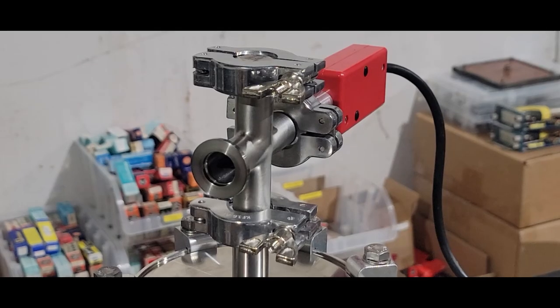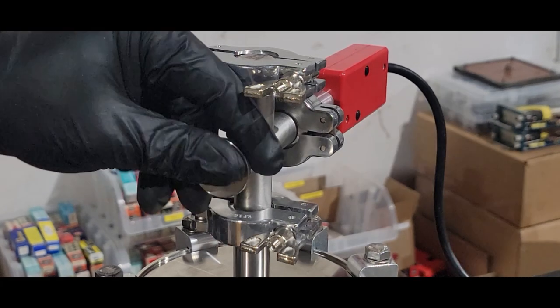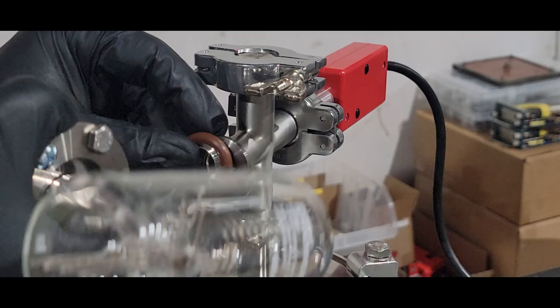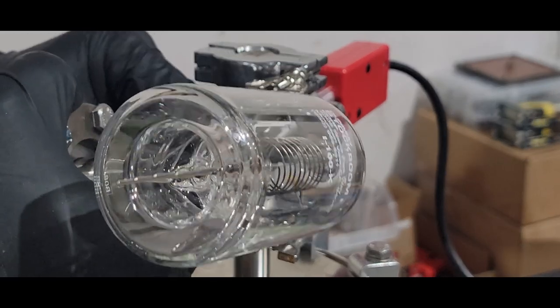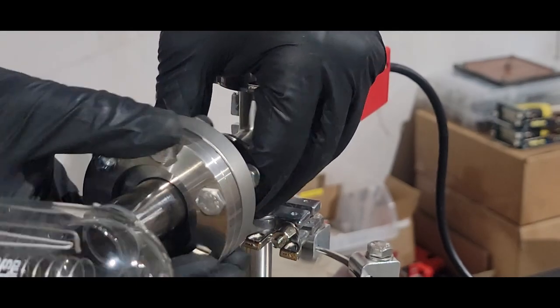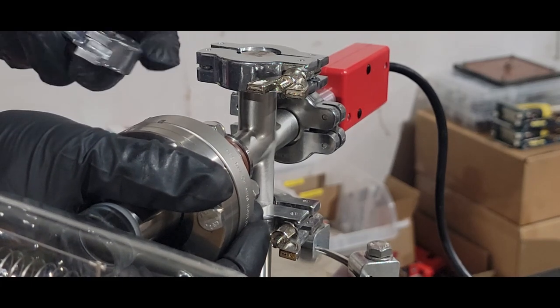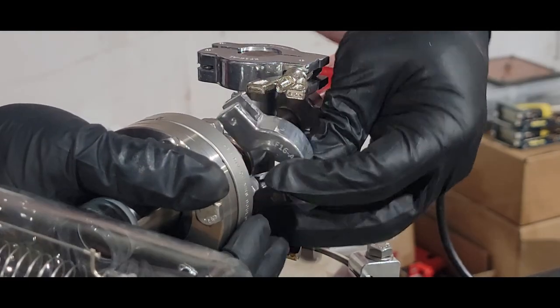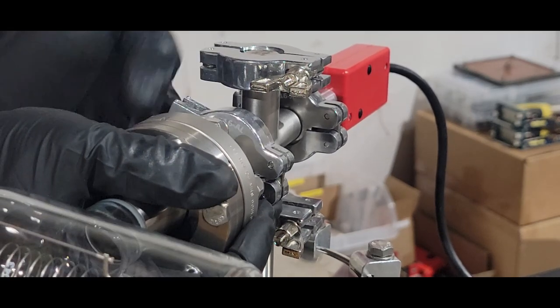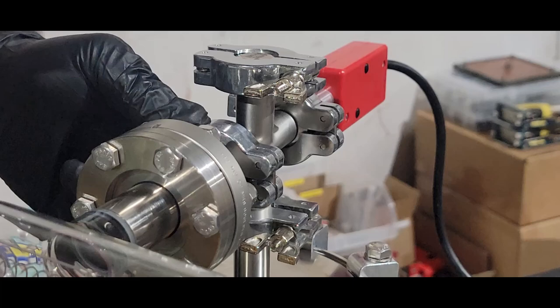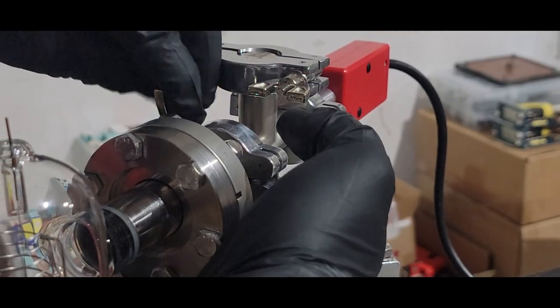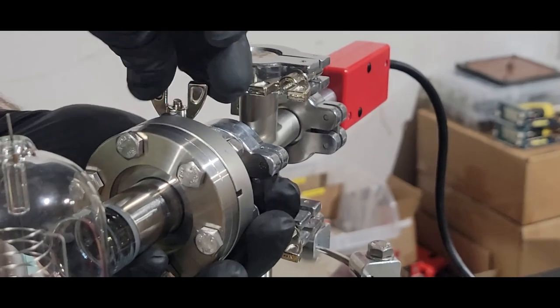Already, you can tell that a vacuum system may comprise one or more vacuum chambers, as well as several vacuum pumps, and all of those things need to be connected with some type of fitting. For the most part, these fittings come in three different flavors. The first of these is the KF connector, which is known by a whole host of other names including QF, DN, and NW. KF originally stood for Kleinflange, German for small flange, but in the English-speaking world, it's become synonymous with quick flange. KF is a type of high vacuum quick connect fitting. It works by holding two chamfered flanges against each other with a circular clamp. A metal centering ring keeps the two flanges concentric, while an elastomeric O-ring actually creates the high vacuum seal. KF fittings work all the way up to ultra high vacuum, and depending on what the O-rings are made out of, they'll even survive bakeout.